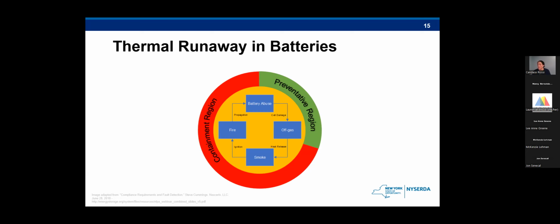But if this off-gassing continues, it may begin to release heat, which will cause smoking. This can translate to ignition and then to a fire, which may propagate and cause more battery abuse throughout the whole battery system. So once thermal runaway has started, it really cannot be stopped.